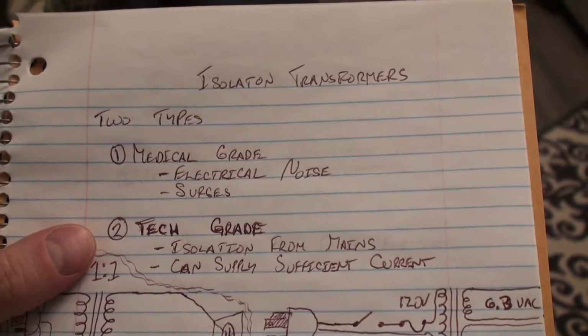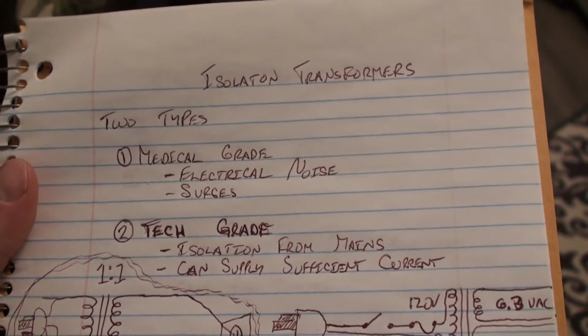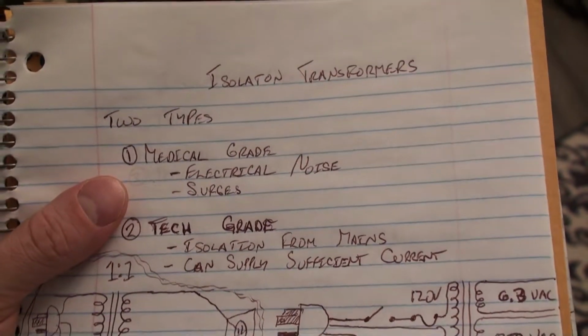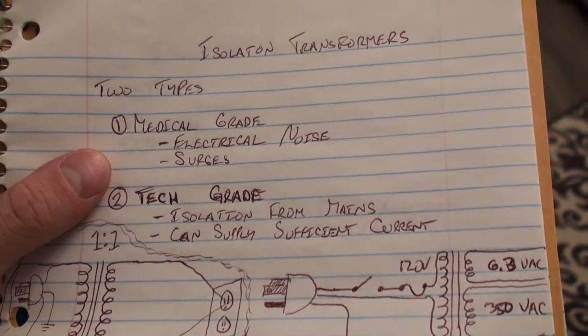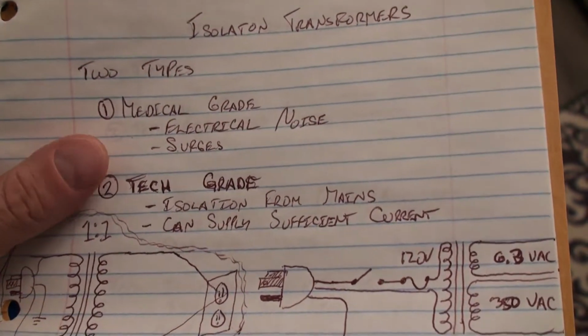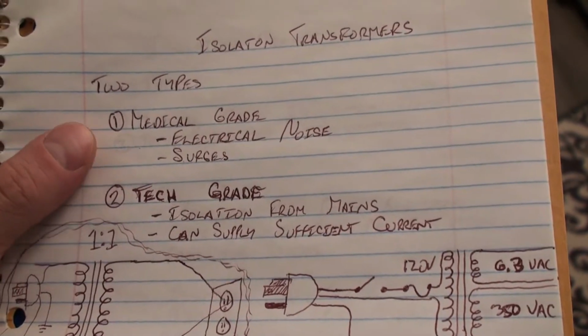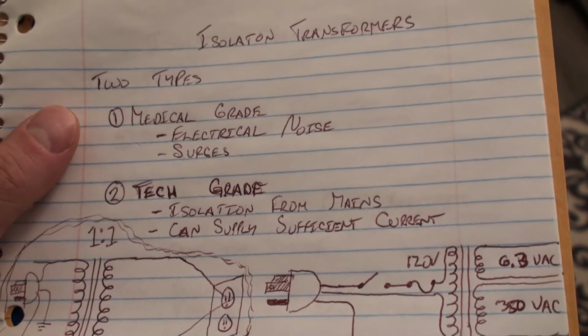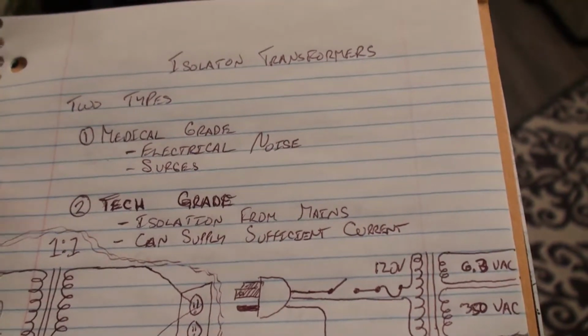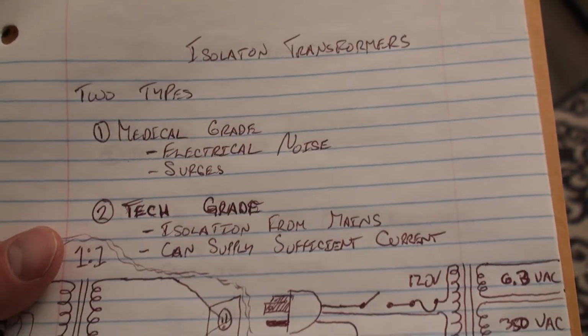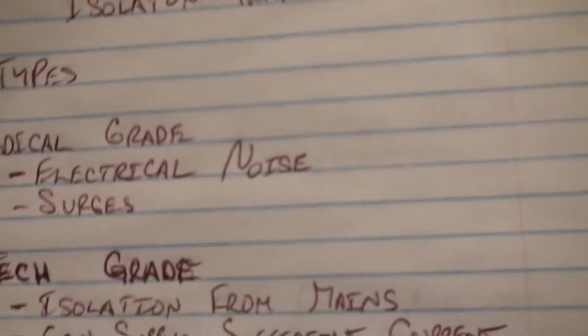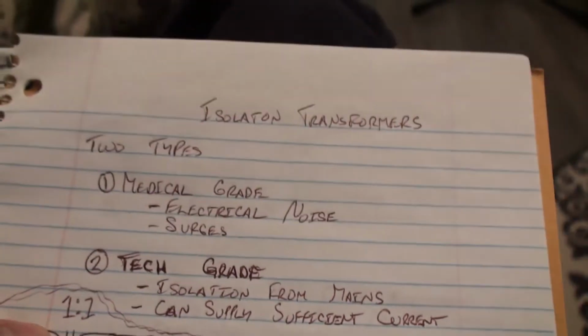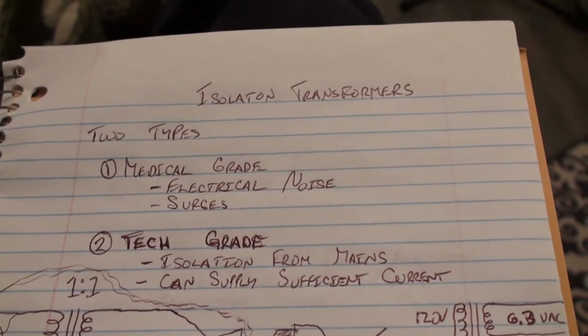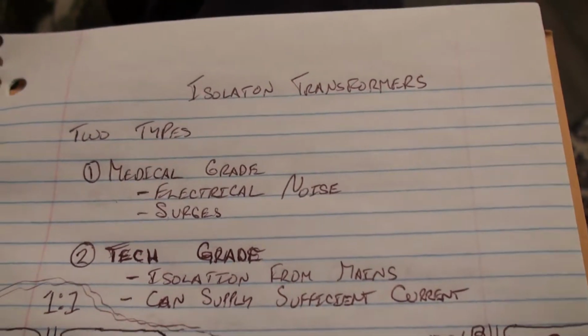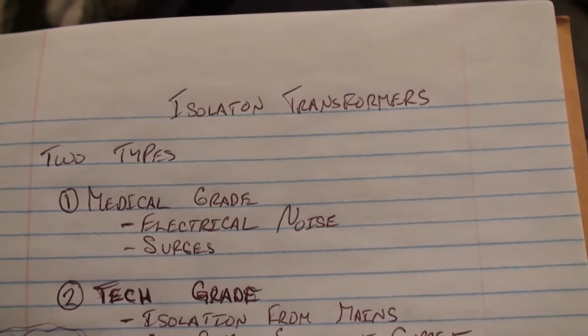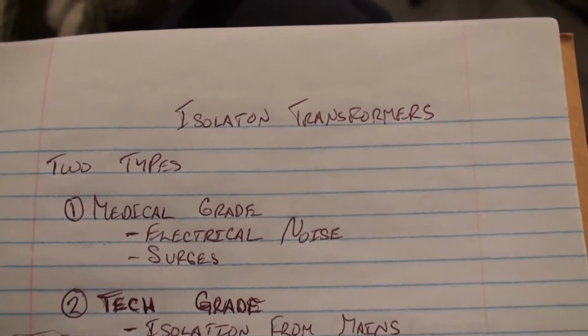There are two types of isolation transformers, unfortunately, and they're both called isolation transformers. The first type is the medical grade. These are used in hospitals, and the main purpose is to isolate the equipment from electrical noise, power surges, and those sorts of things. In a hospital, there's a lot of equipment that's really, really sensitive. You're dealing with the body, and the body has very small electrical signals, so any type of noise on a line would affect that equipment in a negative way.